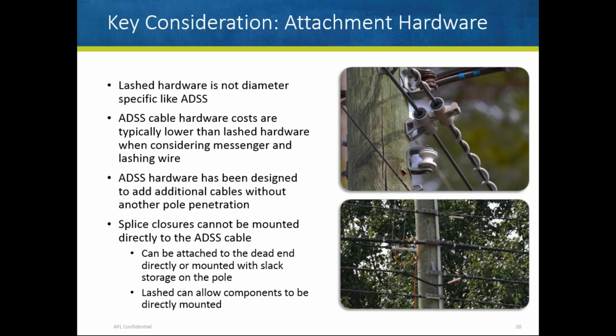There's been some innovation in ADSS hardware. We talk about overlashing to add additional fiber cables into your network. You can see the picture here on the top right of a tangent hardware for ADSS that utilizes two positions that can be added. The second can be added pretty easily without needing to take down the cable or add another pole penetration point, which can be beneficial. We talked about splice closures not being able to be attached directly to the ADSS cable. They can be attached to the dead end and the back of the dead end, as we talked about in the ADSS graphic a couple slides back. But lashed does allow for components to be directly mounted, which could be a benefit.